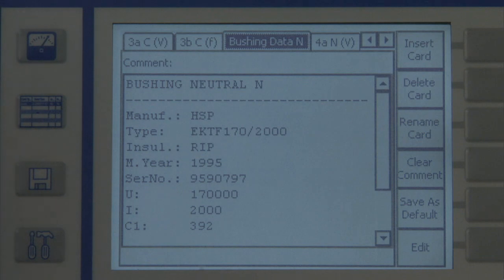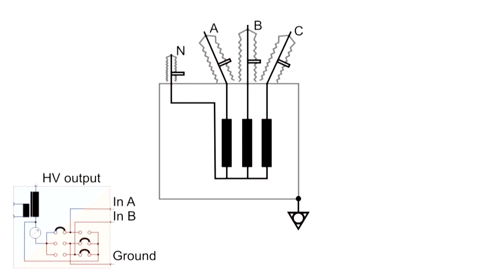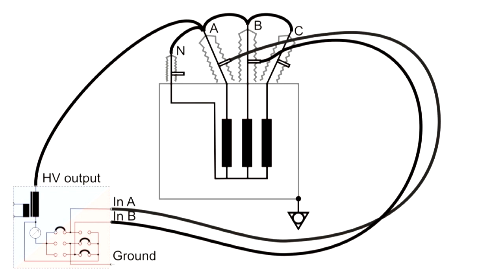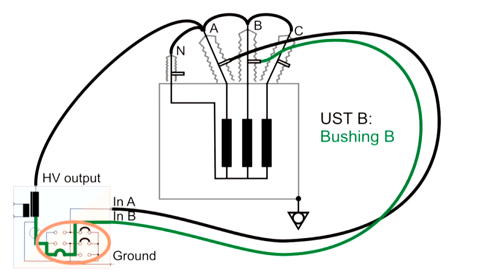To measure the four bushings of our transformer, we start with bushings A and B and connect the test leads accordingly. In the first test card, USTA is set. This setting allows measuring bushing A. Without rewiring, we can continue with measuring bushing B, because the next test card now switches to USTB mode.